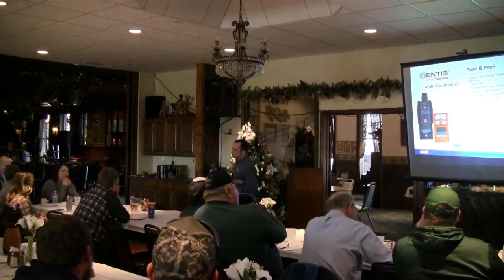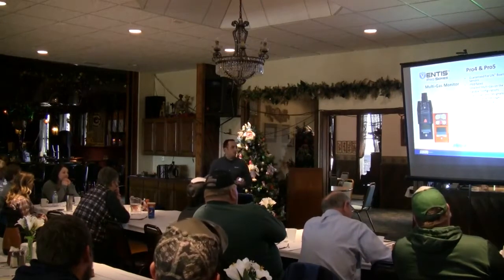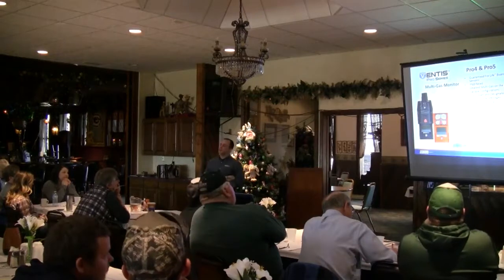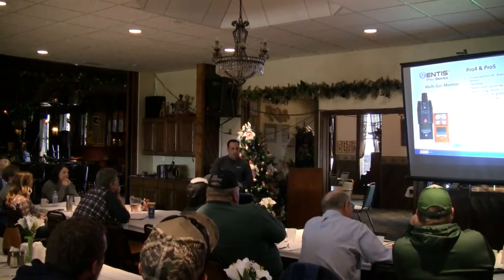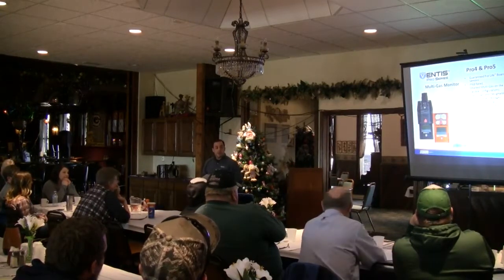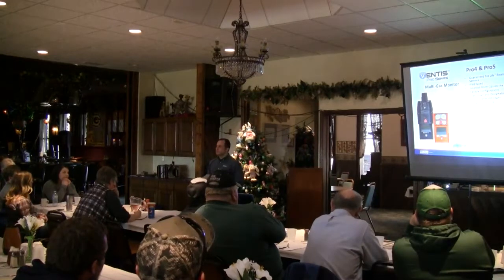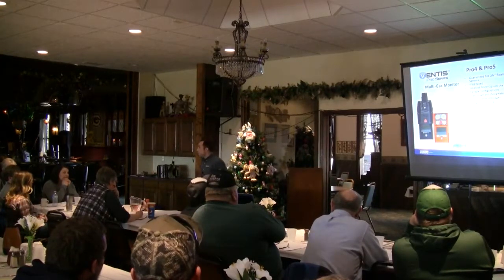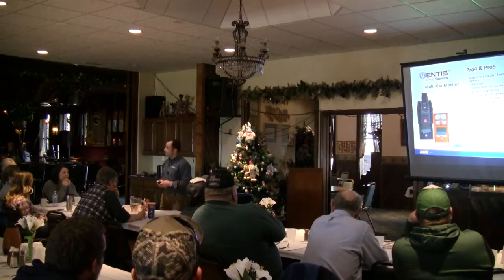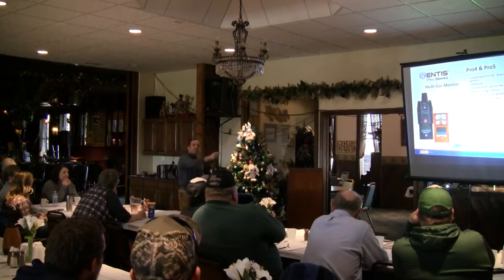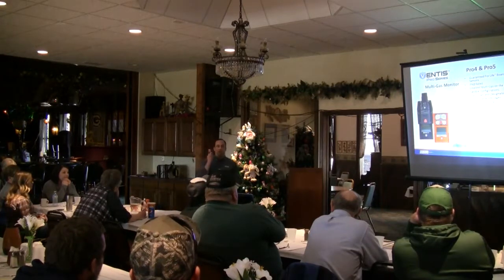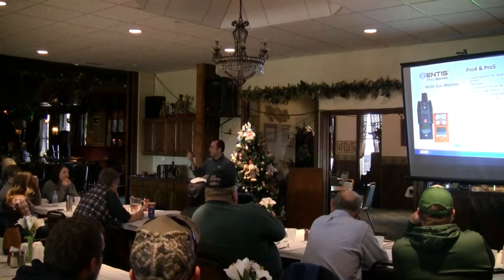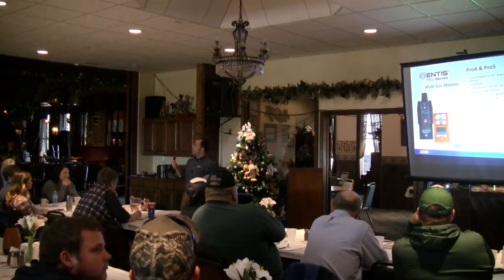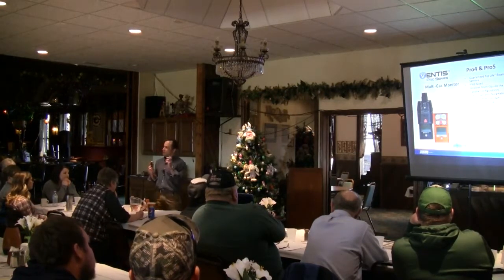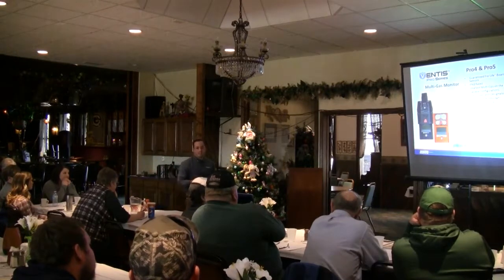The other thing you could do with these devices is, say I put one of these area devices by the pit and it starts going off and I want to go turn off that pump and determine if it's safe, I can remotely peer into that device using this device. So I could actually look at the readings from that device using my instrument in front of me. So I can tell what that instrument's being exposed to at a distance. Right?